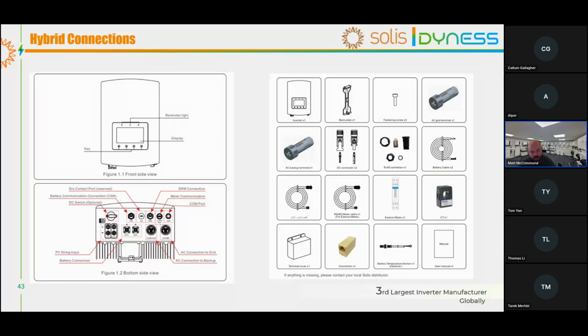The BMS does most of the calculations from what actually is required, how much power we can take, how much power we can put in. It'll all be driven from the BMS sending a signal to our inverter for how much current we can put back into the battery. And then we also have another thing called the DRM port, which is not hugely popular, but all of our inverters do have that, and it's ultimately just a 2-wire start. If you enable that function, you can turn off the AC or open the AC relays to stop production. Normally, that's if you are using a backup generator on site and you didn't want to be generating any power at the same time as running a generator, in case you come into issues with backfeeding.